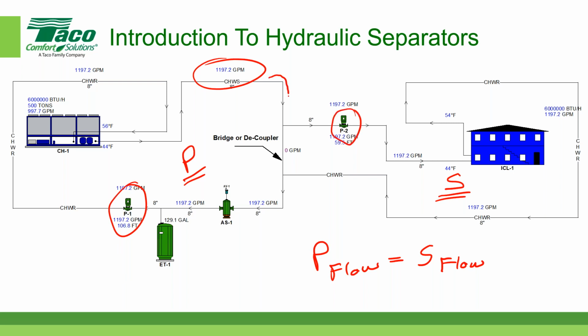So the flow comes around the corner here, and then it peels off and goes in this direction because my secondary pump runs back, and then it comes back at 1,000 gallons per minute. I'll write that over here. And let's see, it goes around the corner here at 1,000. And so the flow across the bridge, in this case, is 0 gallons per minute. So the first case is when the primary flow is equal to the secondary flow and we get 0 flow across the bridge. That should be pretty straightforward.